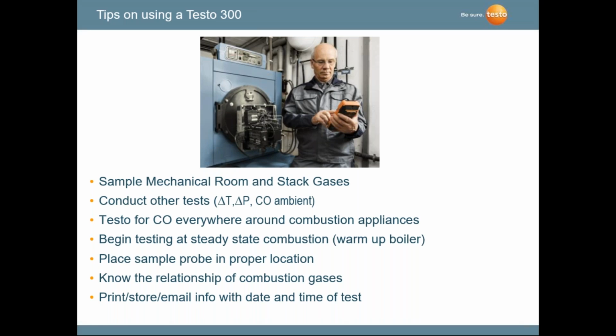Good thing to do. You can look at steady state combustion. That means that when you're doing a combustion test, typically you want the boiler to warm up to a certain point where it has its highest stack temperatures, everything's being mixed properly, and then you would do your combustion efficiency test. Placing the sample probe in the proper location in the stack is important, knowing the relationships of combustion gases, and then taking those readings before and after, and either storing the readings or printing the readings or both, by time and date of the test.